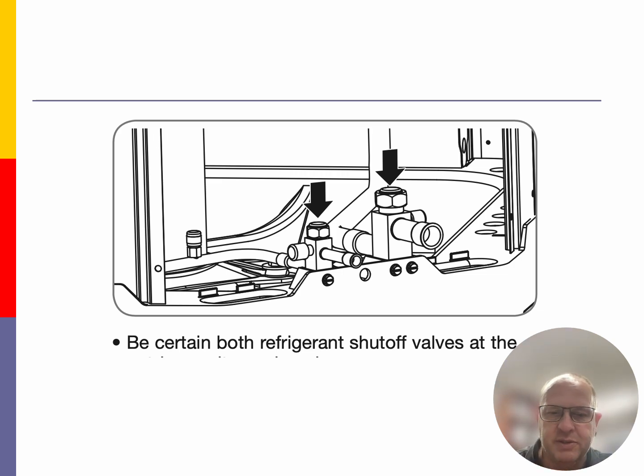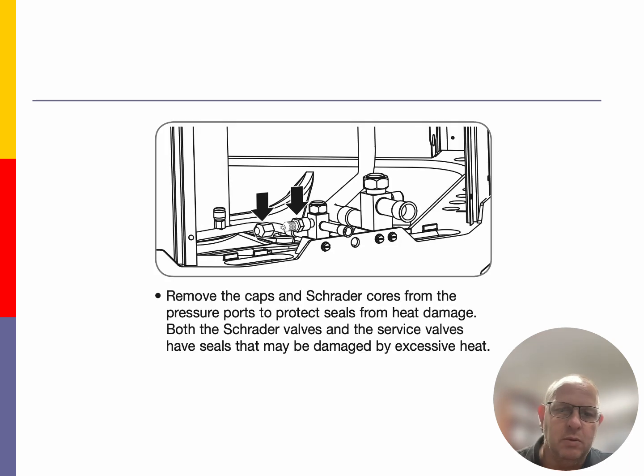Remove the caps from them, remove the Schrader cores from them. And that's being depicted here by this picture. These are service valves, liquid service valve, suction service valve. Take the caps off, take the Schraders out. And before we start brazing on this particular unit, we want to protect it from the heat that we're going to be placing on this copper because we don't want it to damage those things. And that's why we're removing them. Excessive heat can actually damage these valves, especially the neoprene gaskets that are on the inside of them.